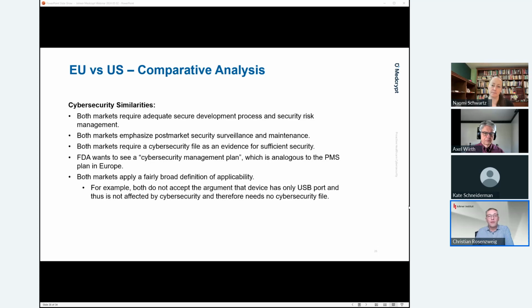Yeah, the next slide about similarities. Both markets require adequate security development processes. FDA is quite open. They say it's a recognized consensus standard to use the 81001-5-1. In Europe, it will be more binding because it will be harmonized, but you can also use the NIST framework in the US market as a kind of total lifecycle process framework. And the security risk management process is always based on ISO 14971, and may be implemented according to AAMI TIR57 or the AAMI or ANSI SW96 or the TIR97, because those are state-of-the-art requirements regarding risk management for IT security.